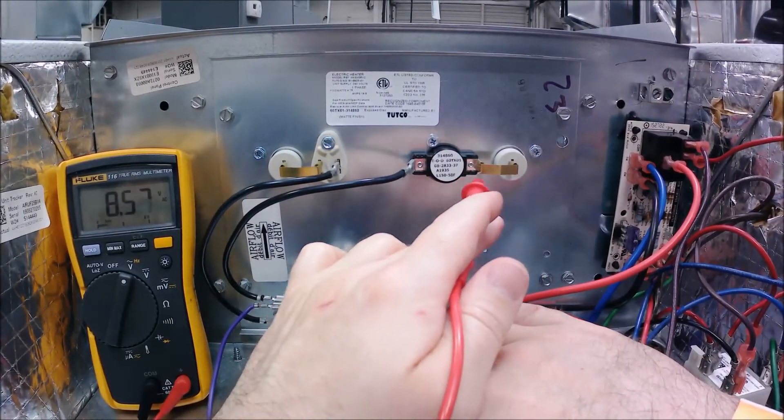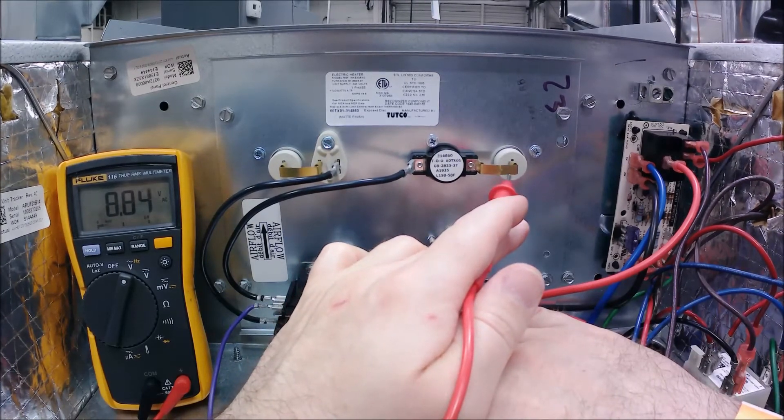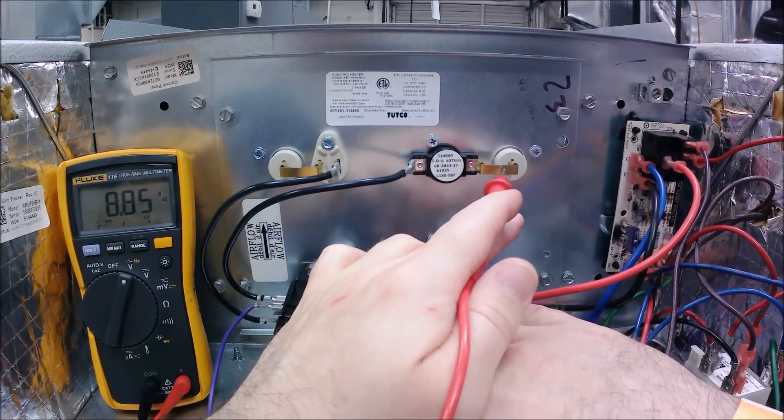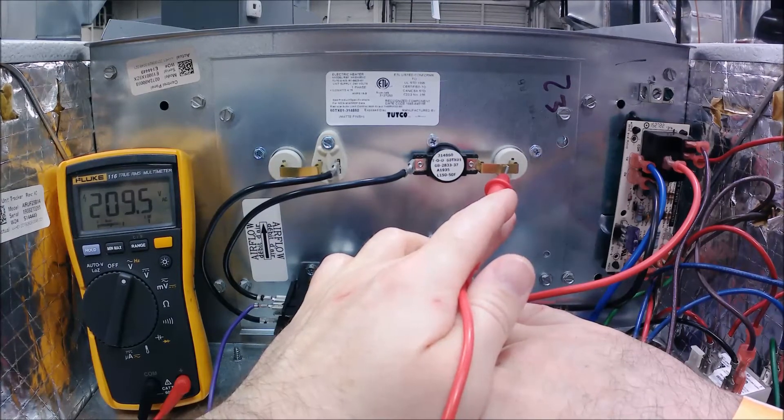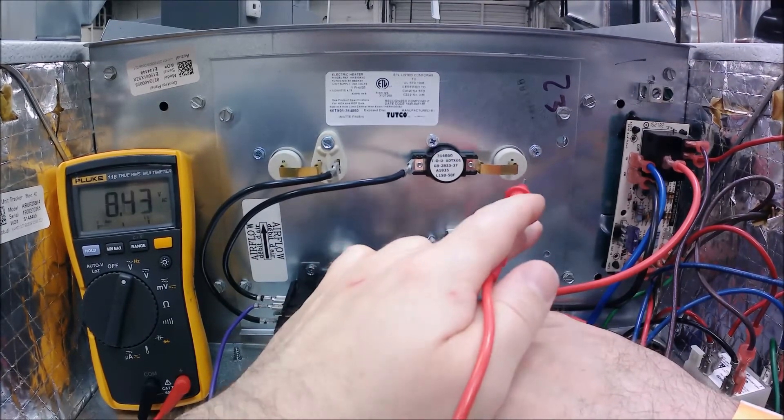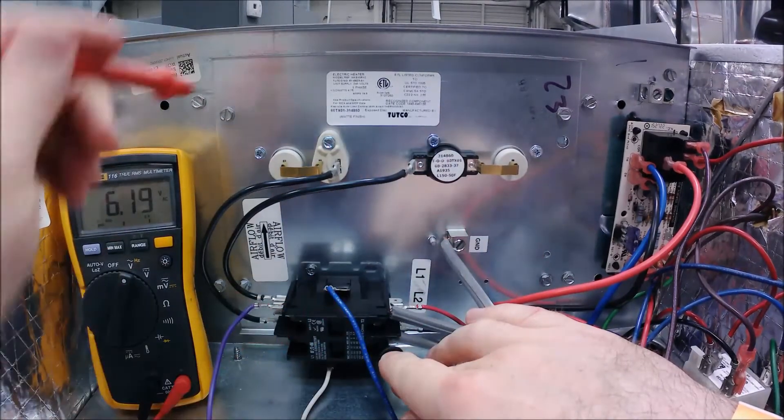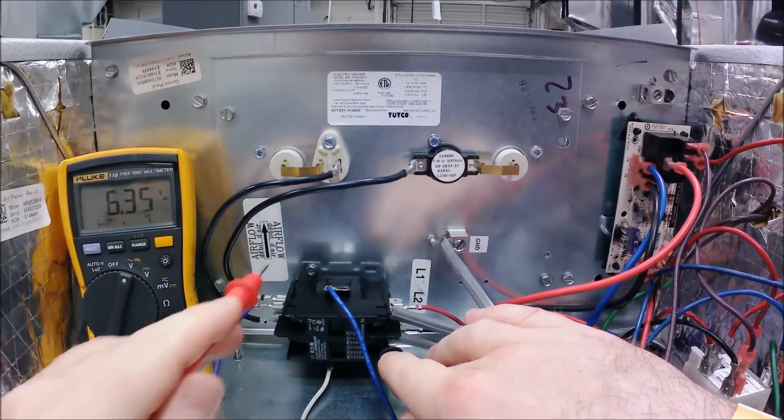This little brass looking clip right here - once it leaves the high limit it's going to go into our heating element. So I can touch right here and you can see I've got 210 volts. I've got full power going in. When it goes all the way through, loops around with the coil, it's going to come out over here.